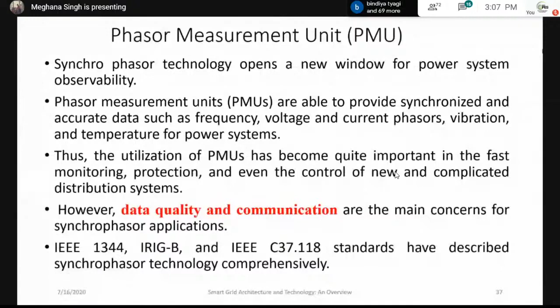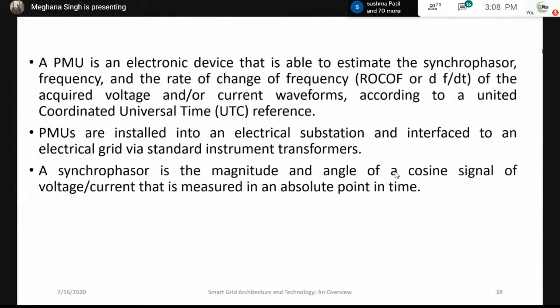A PMU is an electronic device used to estimate the synchrophasor frequency and rate of change of frequency, acquiring voltage or current waveforms according to Coordinated Universal Time (UTC) reference, time stamped through GPS. PMUs are installed in electrical substations and interface to the electrical grid via standard instrument transformers. Synchrophasor is the magnitude and angle of the cosine signal of voltage or current measured at an absolute point in time.